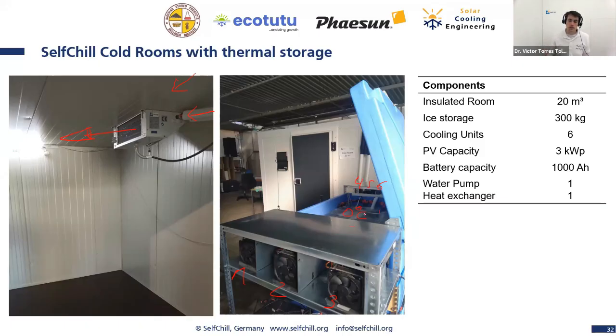So we have here water at 0 degrees going inside the cold room. We have here then water at around 2 degrees. And then we deliver cold air at around 4 degrees, so that the temperature in the cold room can be around 5 to 6 degrees. This is our minimum, but this is a design, right? If you want to have the cold room temperature a little bit higher, then you need less cooling energy, you need fewer cooling units, you need fewer PV panels.